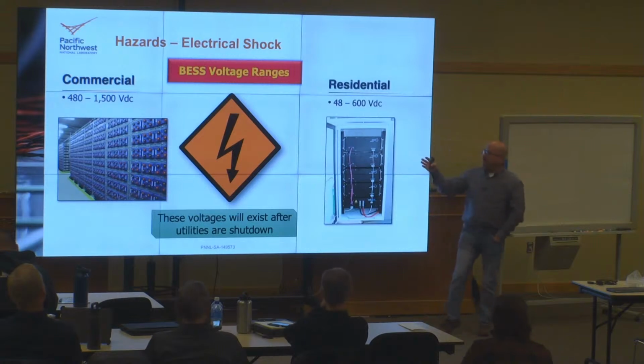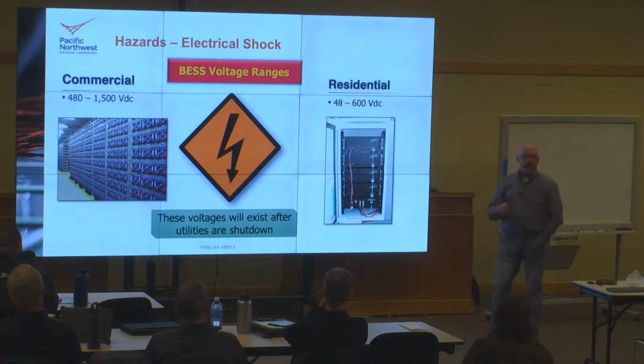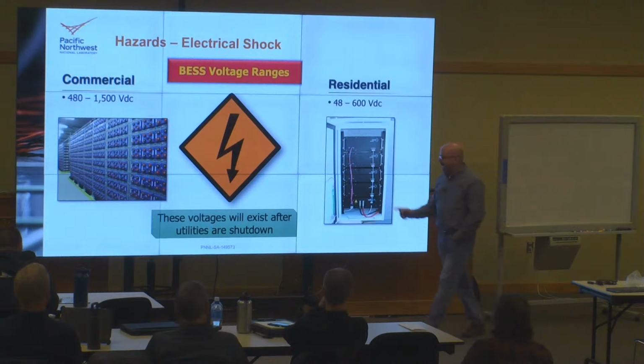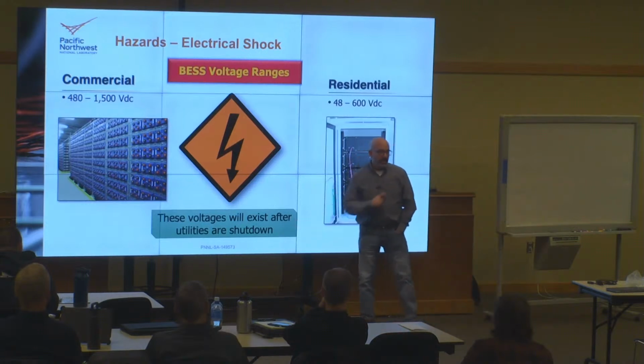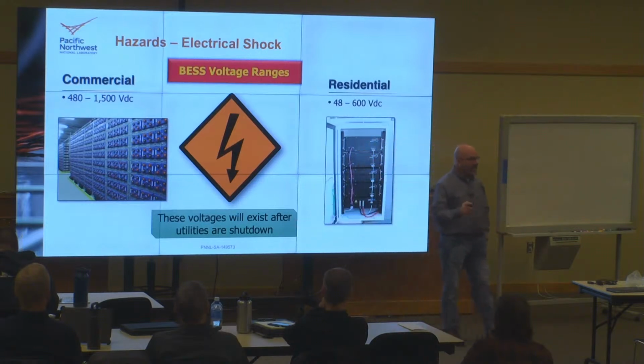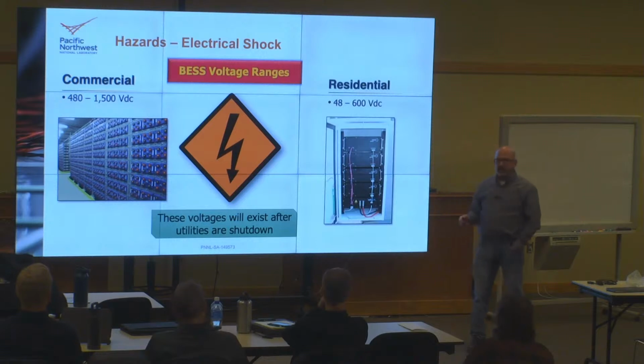On the commercial side, voltage typically goes from around 480 volts up to 1500 volts. What's key — and I keep trying to point at the screen — these will exist even after utilities are shut down. Even on a residential system, once you shut off all the disconnects you see, the batteries are still energized. I think you all understand that now.